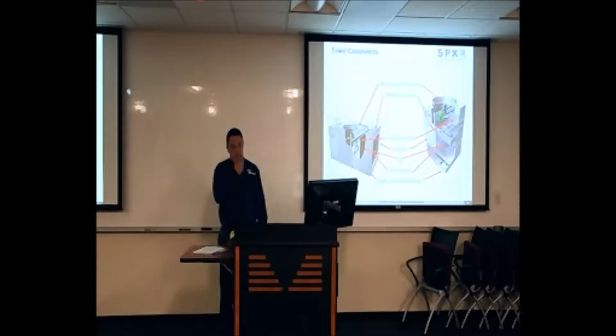I found these drives to be very reliable. What I've come across the most is whenever they do fail, I've had them with dust intrusion. Since they all have cooling fans, they all end up bringing in some kind of dust. And typically guys never ever blow them out. Usually I've seen that if the guys blow them out every 6 months, tighten up all the connections, and make note of any kind of overtemp, you're going to have reliable service out of the drives, 10 to 15 years.